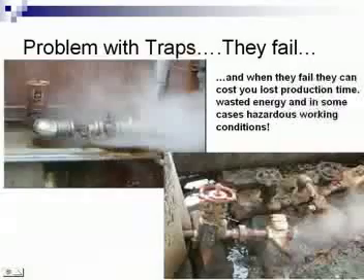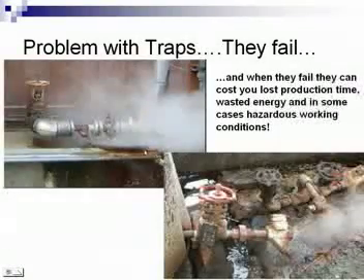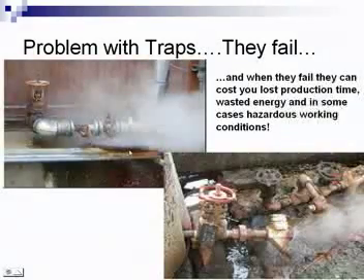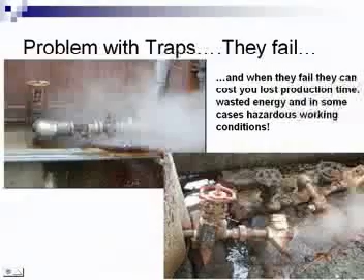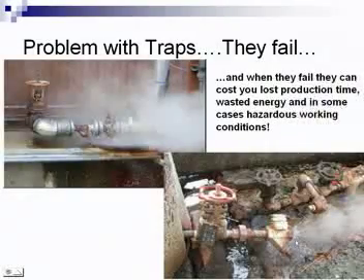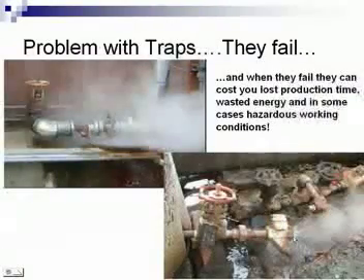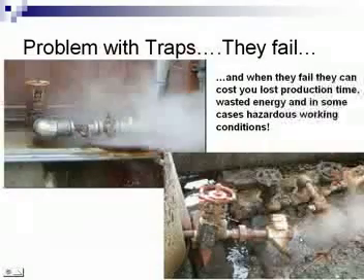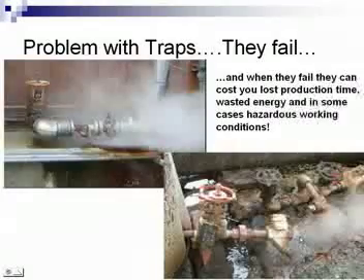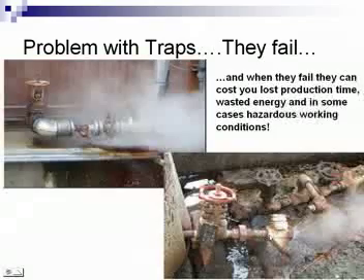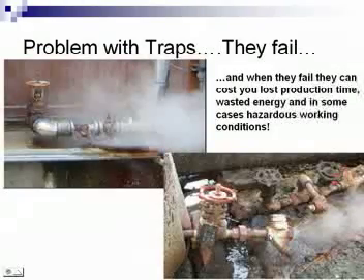This is a typical steam system that's been neglected. In the upper left-hand corner we're depicting a steam trap station that is having leak-by, corrosion, and many other problems. On the right-hand side we're showing a disconnected steam trap that's obviously in a fail-open position. And if you look very closely, it's been tested — there's a tag hanging off of the valve. Just testing the trap is not the only thing you should do; you need to replace and repair it to reap the benefits.